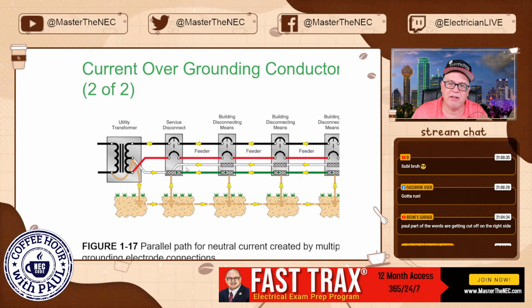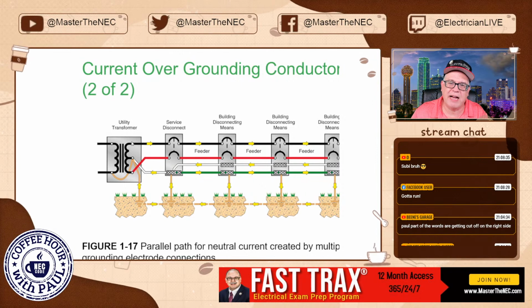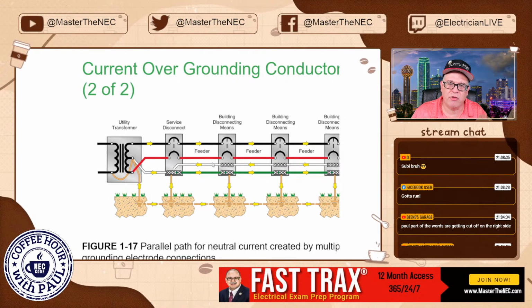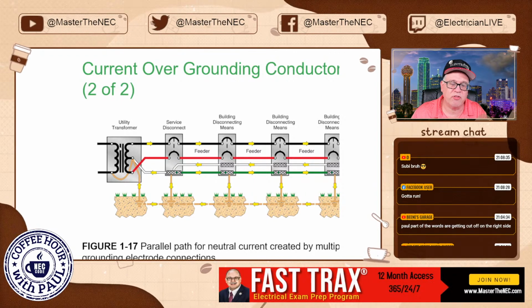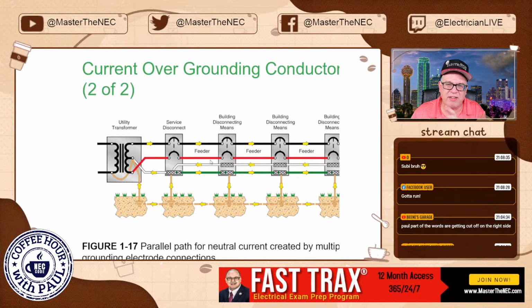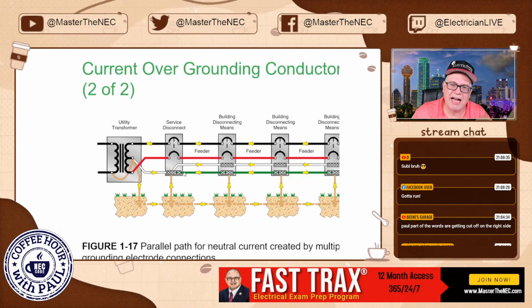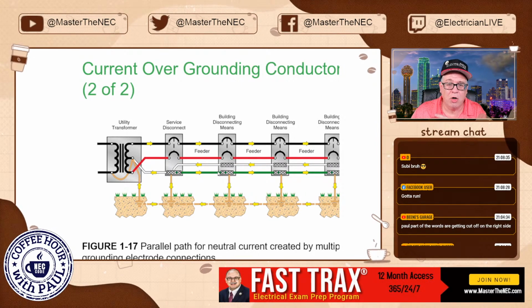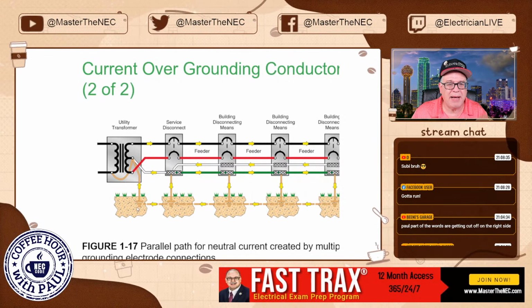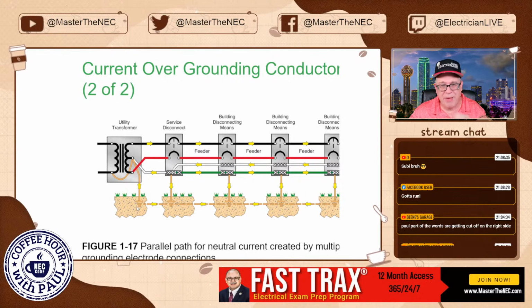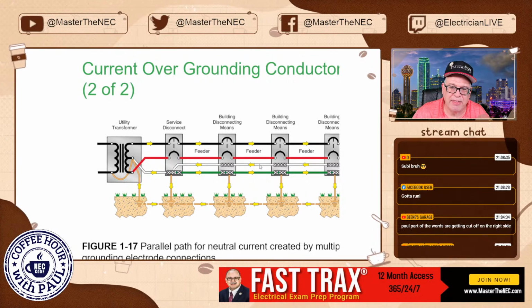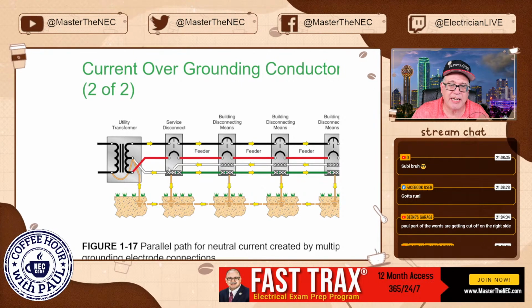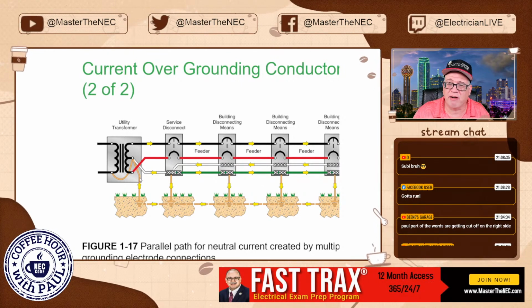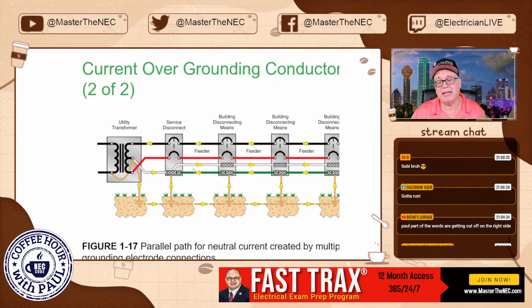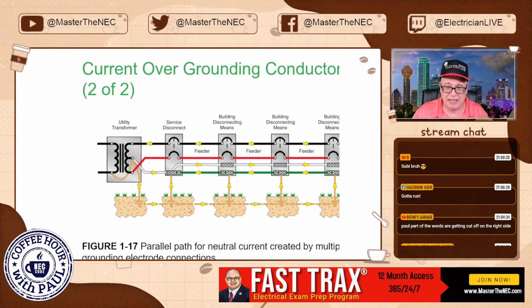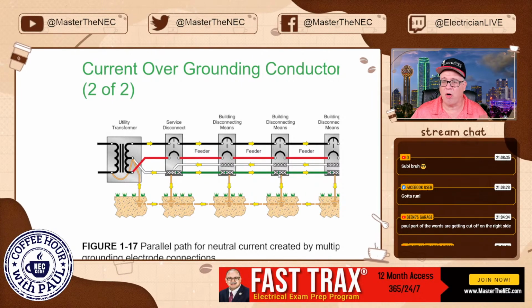But what you need to remember is how this works: here you've got current going through the system and it's coming back on the neutral, but also is going back to the source utility. But since they got multiple ground points, these could be separate buildings, right? Then you'll have current also going back on the equipment grounds to get to earth to come back to the source. So it can travel in all paths, but I can promise you this path, if constructed properly, is going to carry the lion's share of that return current during a fault condition, okay? And that's where you're going to get your overcurrent device cleared, okay? Not the earth. But this illustrates that it travels on all paths, okay?